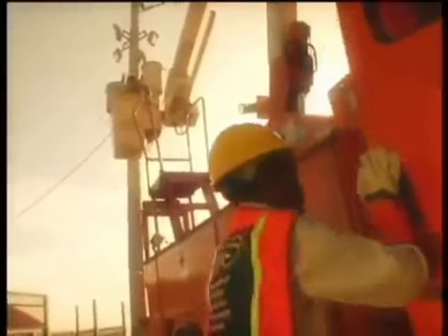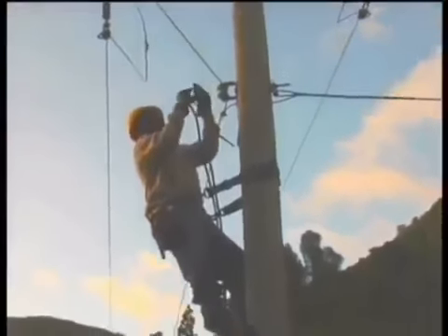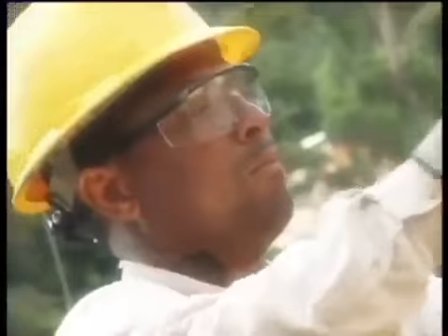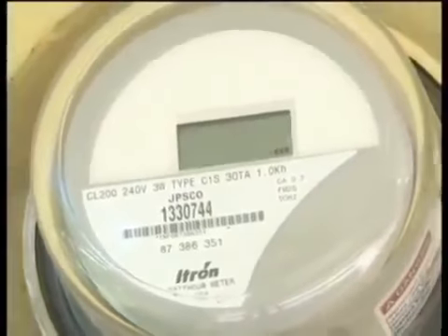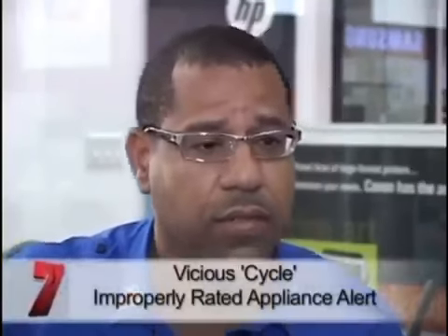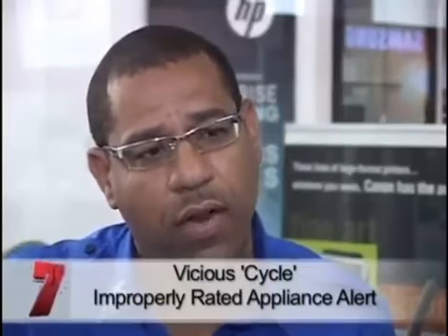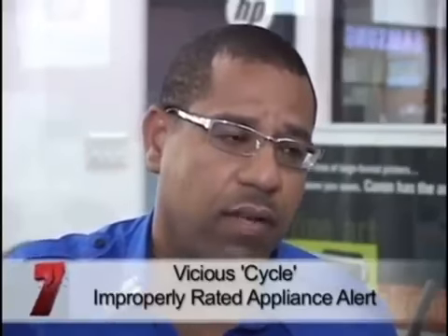So when you use a 60 Hertz appliance on the JPSCO's 50 Hertz grid, this is what could happen. What you're using is losing efficiency. It's nice to talk about a particular piece of equipment like a refrigerator. You would be losing about 12.5% efficiency on the refrigerator, right? And you can also run the risk of burning a compressor. Why? Because the compressor starts to draw more current than it normally would if it was in a 60 cycle environment.